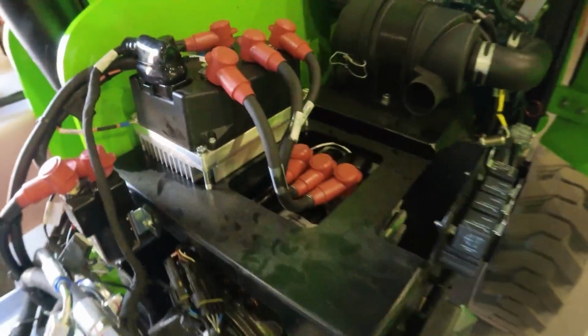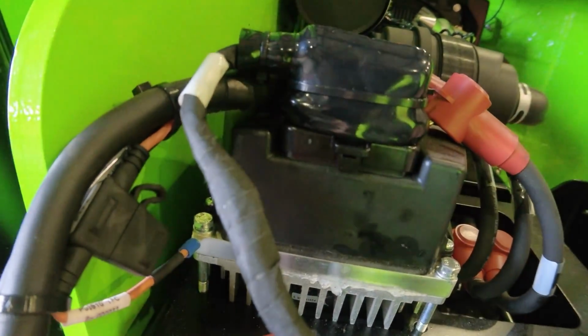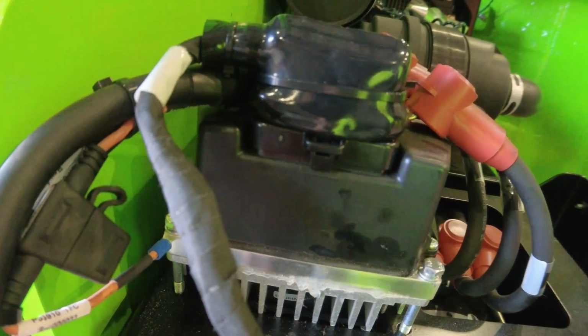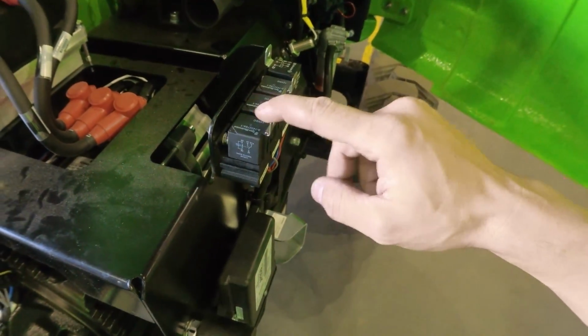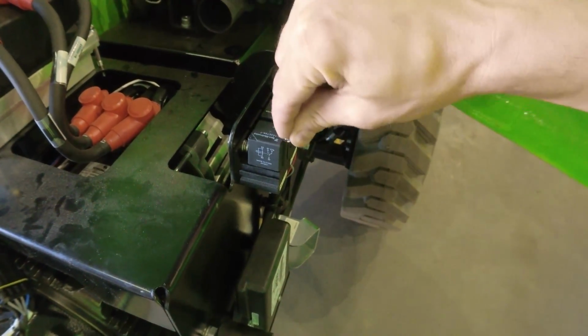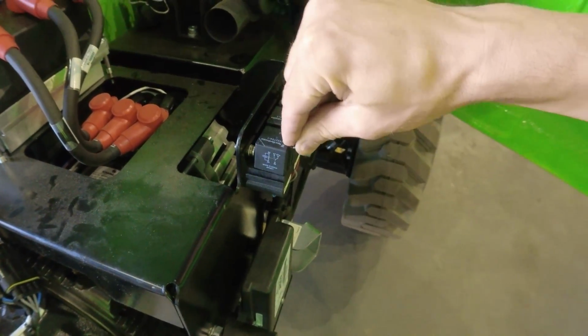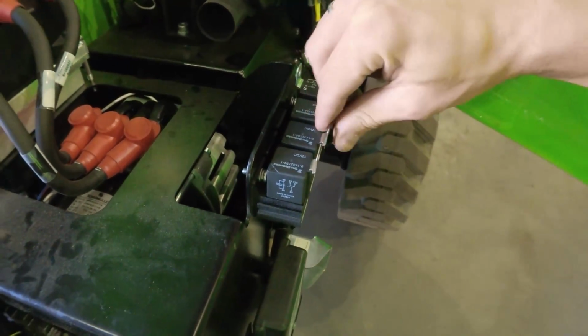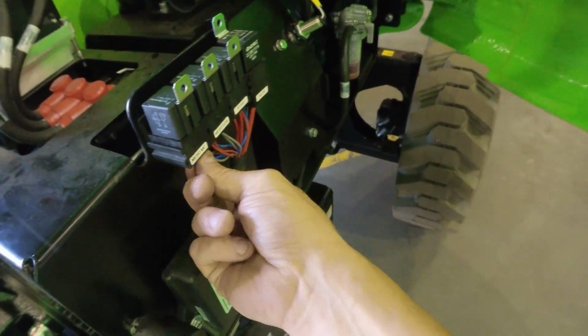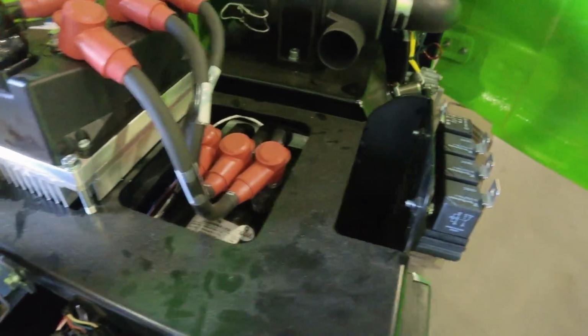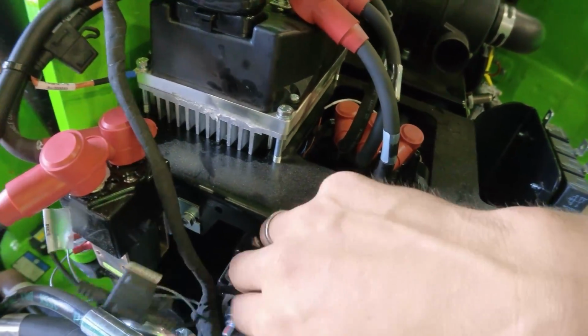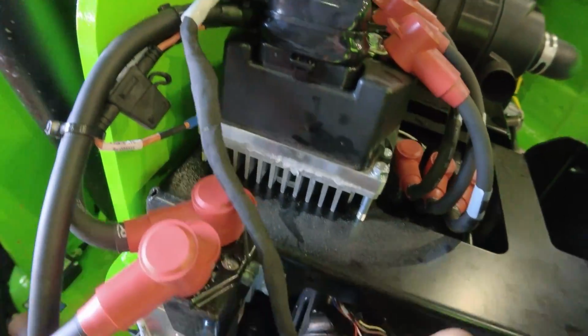Okay, so let's see if we can trigger the fault with the relay. The motor controller is now flashing an amber light, nice and steady, no problems, and I'm going to move the relay. It's all good, no problems at all. Okay, so that was an easy fix. One terminal was loose and that was causing the troubles here. Okay.